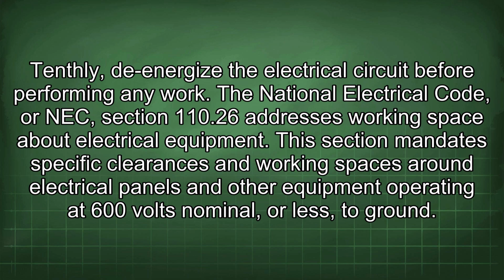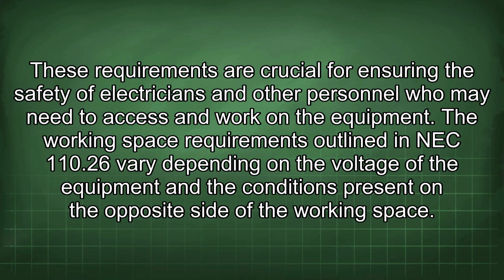The National Electrical Code, or NEC, Section 110.26 addresses working space about electrical equipment. This section mandates specific clearances and working spaces around electrical panels and other equipment operating at 600 volts nominal, or less, to ground. These requirements are crucial for ensuring the safety of electricians and other personnel who may need to access and work on the equipment.